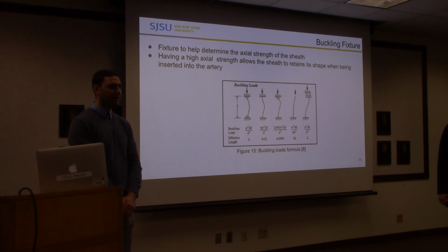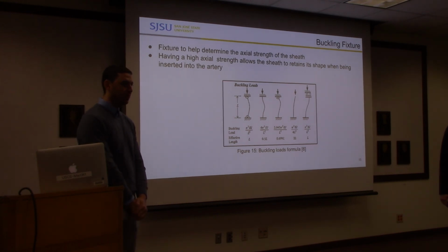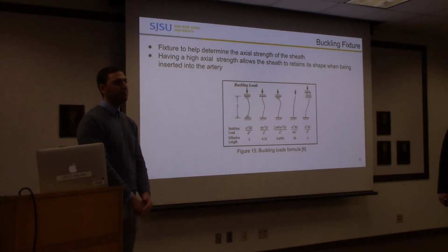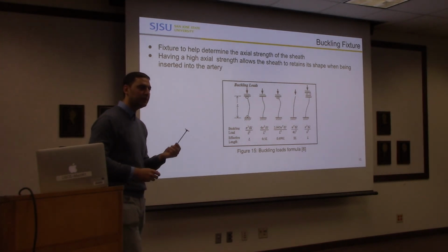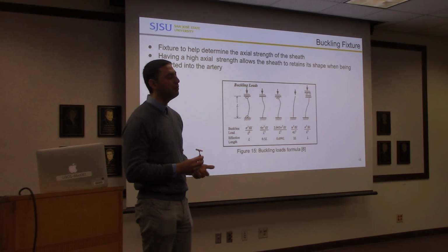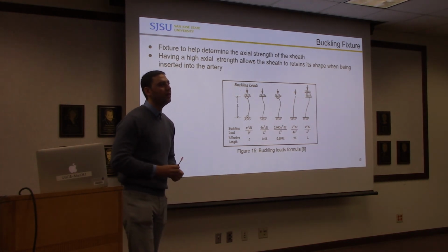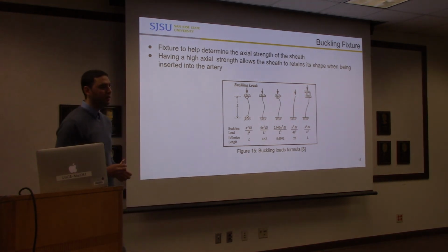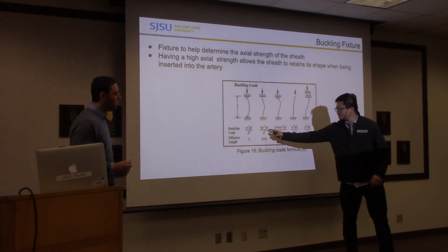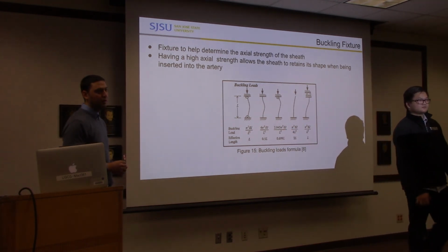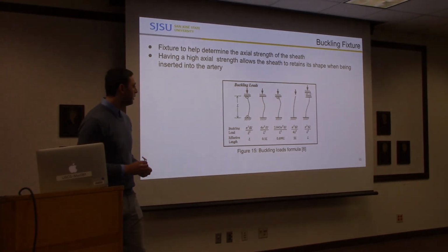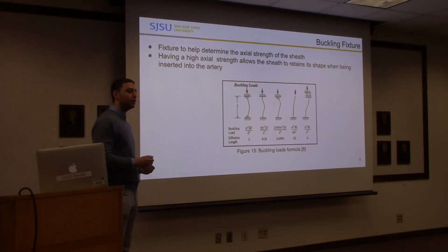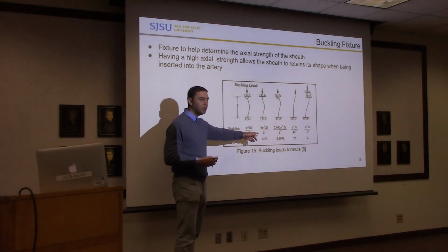So just with that, what are these catheters or these sheaths made out of? There are multiple materials. This one is Marlex, which is HDPE. There's PEBAX. There's also a composite. So these equations assume the material is linear elastic, yeah? Linear elastic materials is what this assumes, with E, the elastic modulus. Is that a valid assumption for these materials?